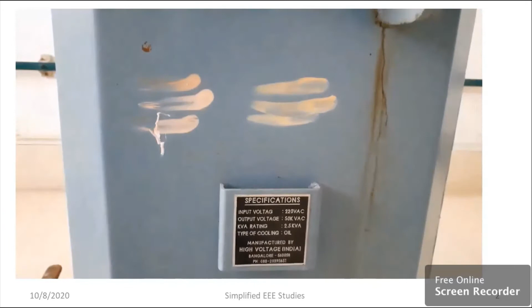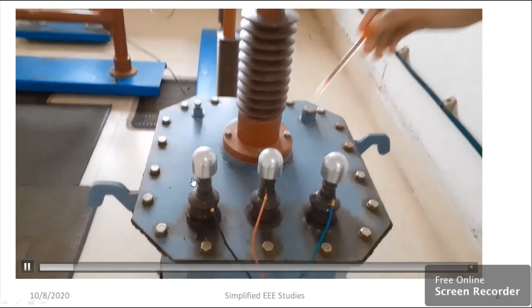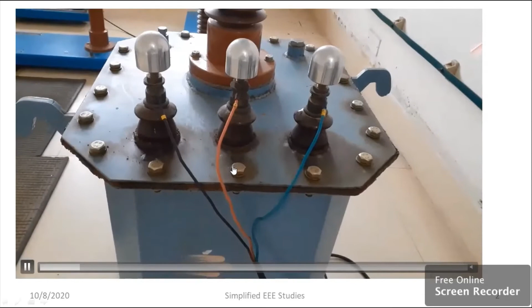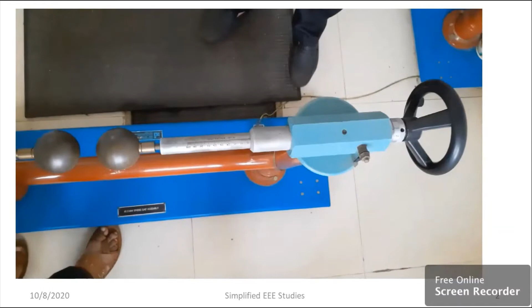For generation of high voltage AC, we require a single phase high voltage AC transformer. That's the peculiarity of this particular transformer. It has three terminals, and the connections are taken from the bushings. The first terminal is the neutral terminal, the second is the phase terminal, and the third is the earth terminal, since three terminals are present for applying high voltage AC across the sphere gap.